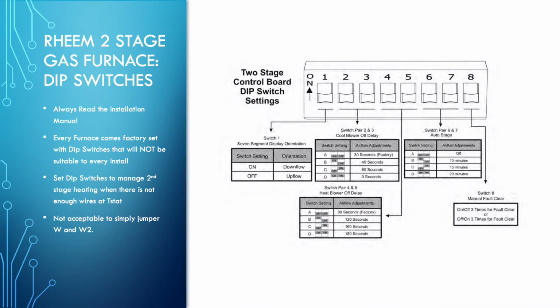Now, the dip switches that you're going to find in the manual, this is an actual outtake from the installation manual when you open it up and you take a look at it. Right off the bat, you need to be paying attention to what the timing is. So if you have the extra wire for second stage at the thermostat, you're going to leave it in the off-off position, which is what it's set for from the factory typically. Now, our company, we prefer to put it at 10 minutes for the upstage to second stage. If they don't have that wire at the thermostat to dictate it themselves or let the thermostat decide when it should do it, then we usually put it at 10 minutes.